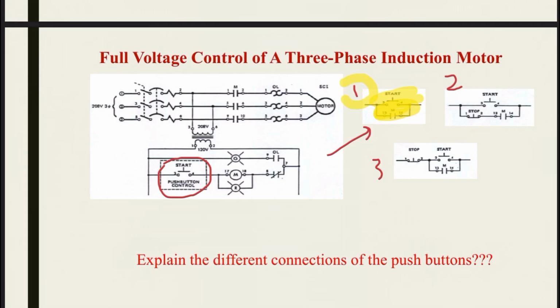For the first one, it will close. Okay, this is the first connection. So will they open when the push button is released? No, because we have normally open contacts here. It will close, so it will keep the motor running. Are they acting as holding contacts? Yes, these are the holding contacts, and we have already explained this contact.